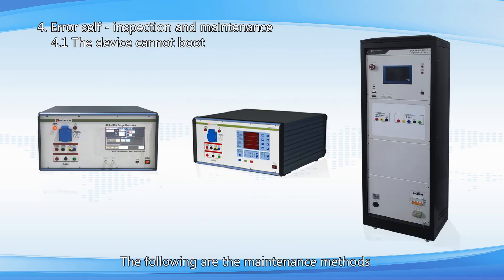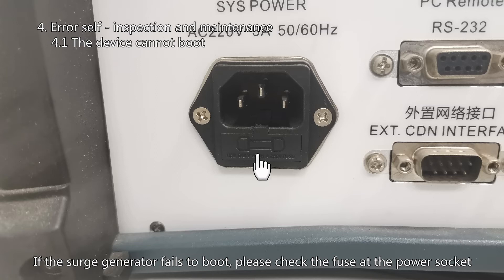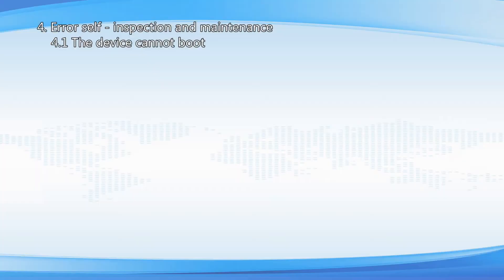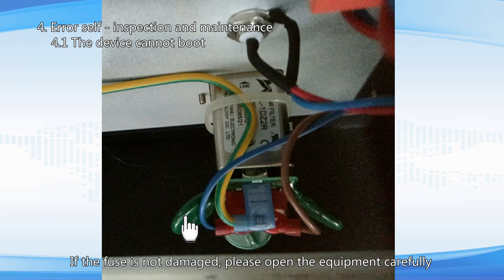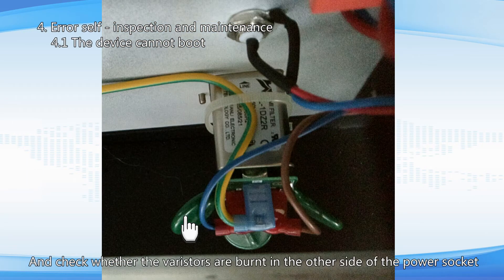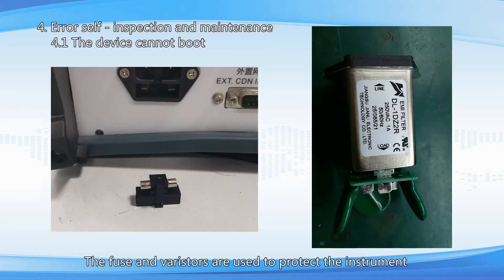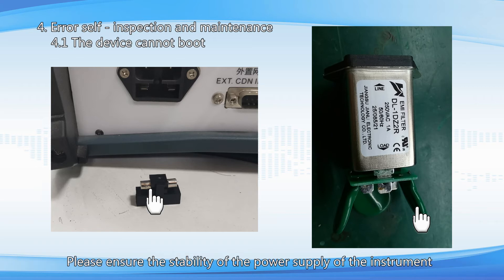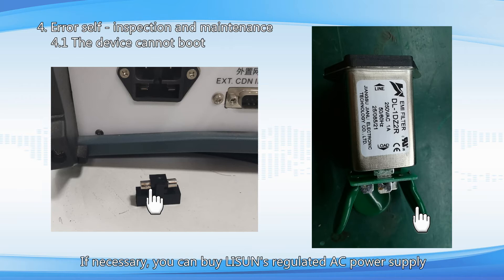The following are the maintenance methods. If the surge generator fails to boot, please check the fuse at the power socket. If the fuse is not damaged, carefully open the equipment and check whether the varistors are burnt on the other side of the power socket. The fuse and varistors are used to protect the instrument. If there is a problem with the power supply, they may be burned. Please ensure the stability of the power supply. If necessary, you can buy LISUN's regulated AC power supply.